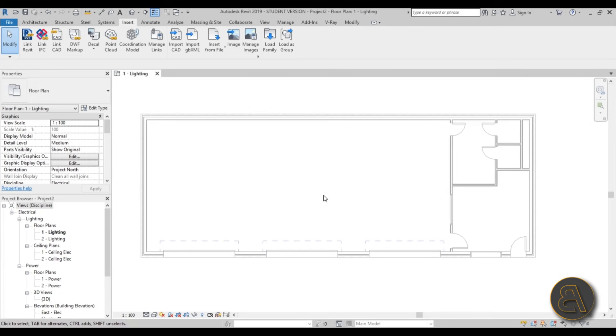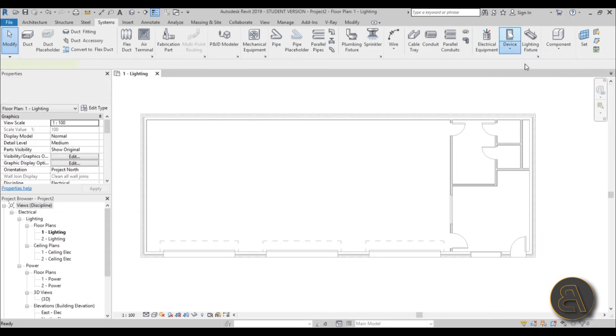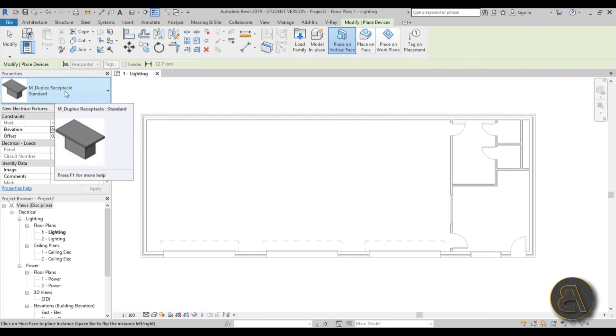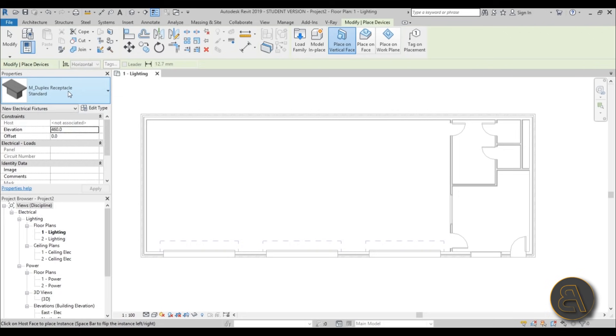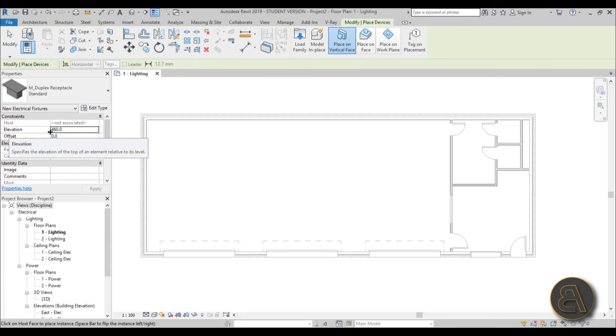The first thing we're going to do is add some outlets. Go to the Systems tab, find Devices, and here you've got Electrical Fixtures. We need the duplex receptacle — we've got only two options for now, so let's use the standard one. If you try to place it on the floor you can't, because it's a wall-based element — it says 'place on vertical face' so it can only be placed on a wall. The elevation from the ground defaults to 460 millimeters, which is a bit confusing, so let's switch to centimeters.